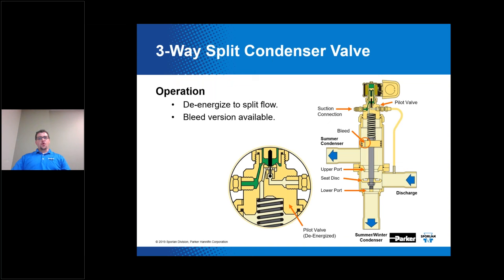Now we're getting into three-way split condenser valves. Splitting the condenser is a method of refrigerant side head pressure control that allows you to reduce the condenser capacity by 50 percent during low ambient conditions. That's typically done using a three-way split condensing valve. I'll cover the operation of the valve and show a diagram of how it's applied.